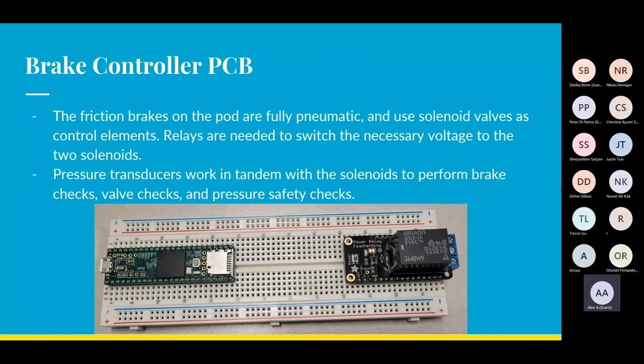They work in tandem with the pressure transducers on the line to perform braking operations, as well as different safety checks for pressure and valve positions.